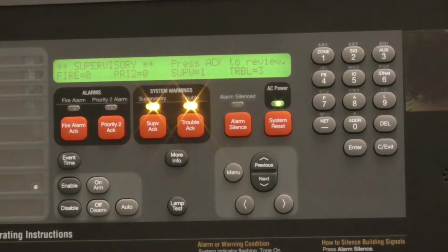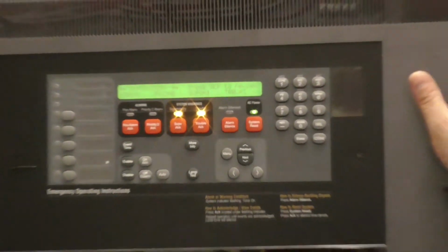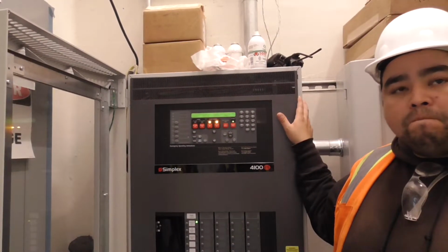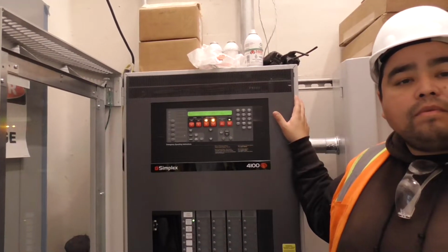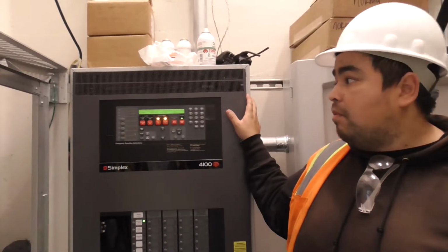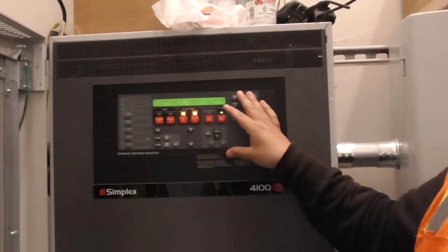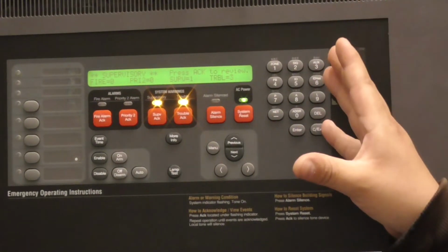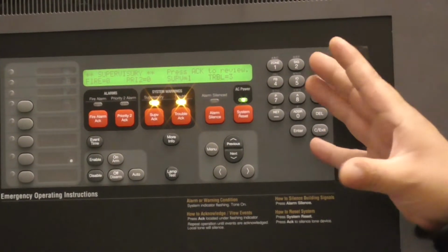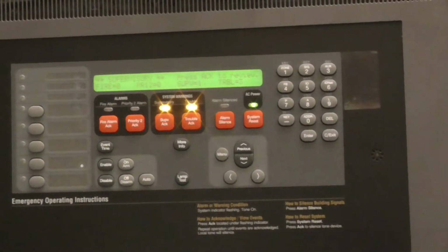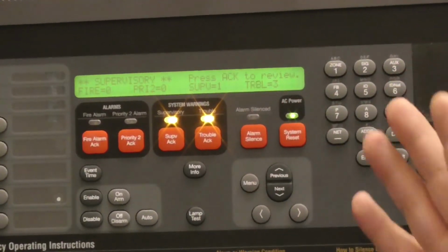Right. So, for example, if somebody removes a smoke detector and they're tampering with it, we'll get a trouble, head missing. Somebody removes a head, you get a head missing. I don't really know how you guys handle that, but it just goes into a regular trouble, head missing. Reports to PD as a head missing.